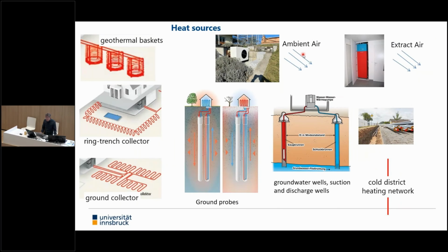Yeah, what kind of heat sources are available? In the ground, there are a lot of possibilities. The deeper you go, the warmer the ground is, but it's more expensive. So geothermal baskets or ring trench collectors or ground collectors, or even deeper, that's the ground probes. You drill holes and guide some fluid in the ground.